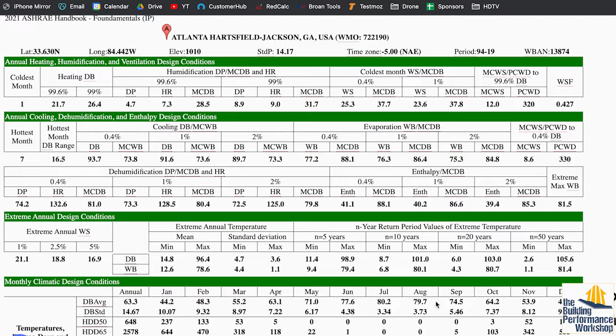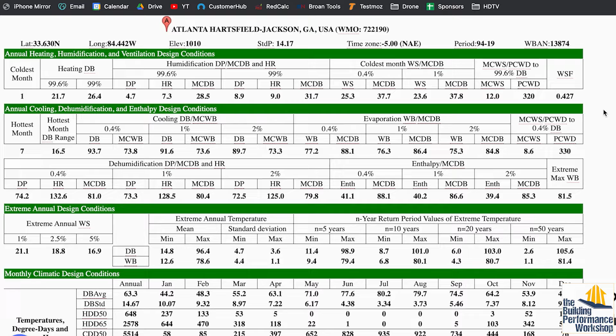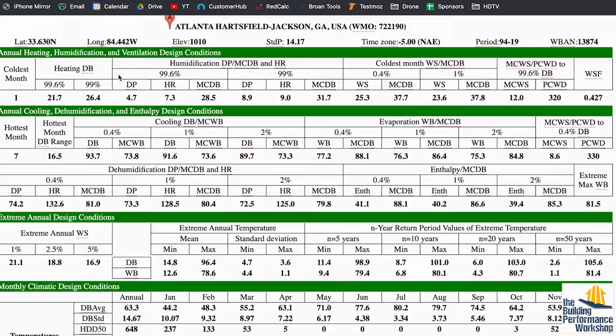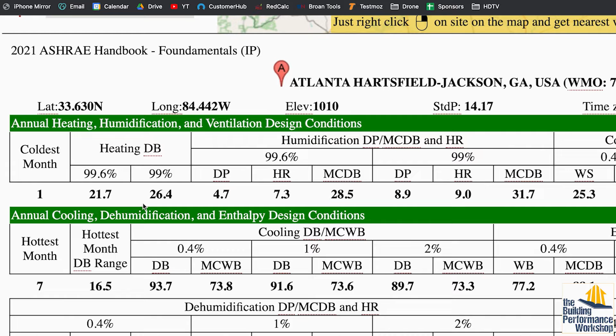But when you look at that 1% day, that's your cooling day—the numbers you're looking at are the 1% dry bulb. So they focus on the dry bulb. We take all the hours of this dry bulb temperature, 1% of them are warmer than this—here's our magic number. And then the number that goes with that is the mean coincidental wet bulb.